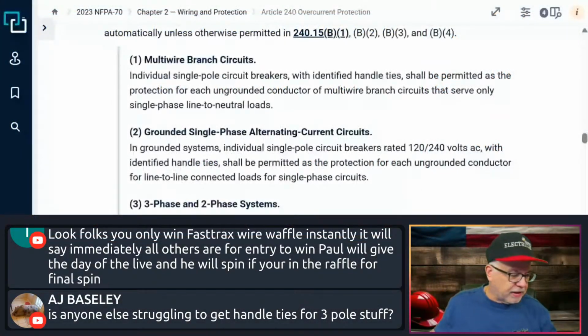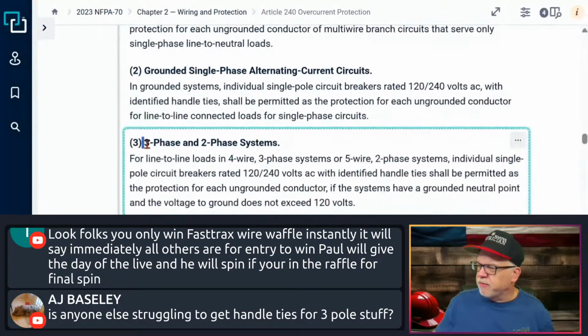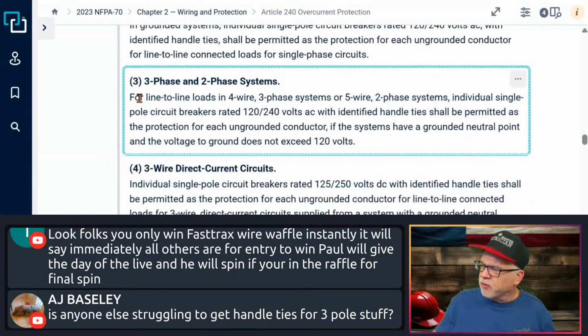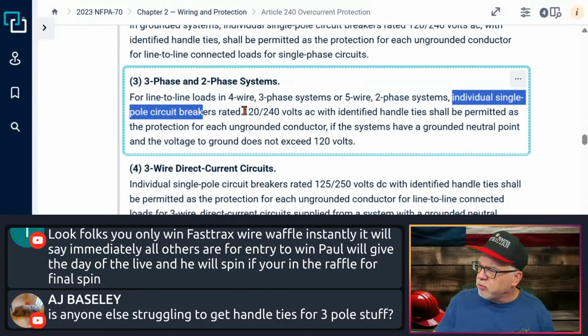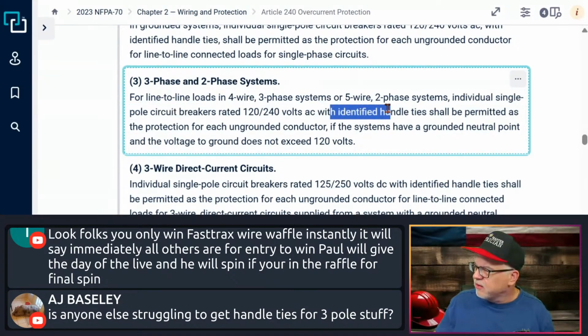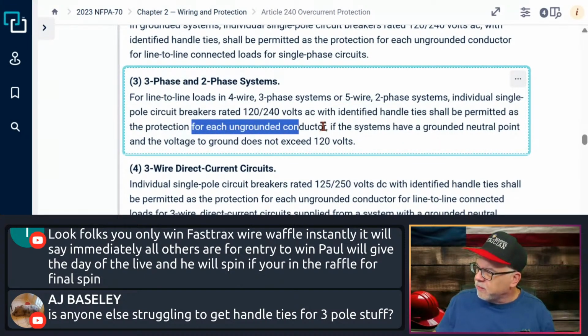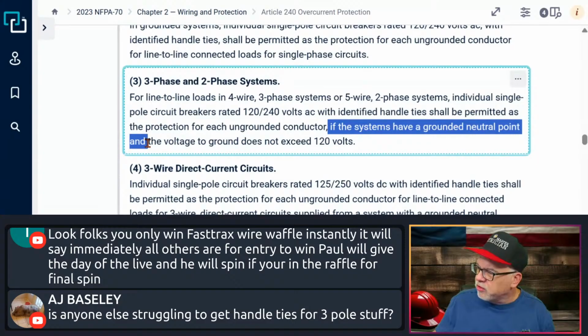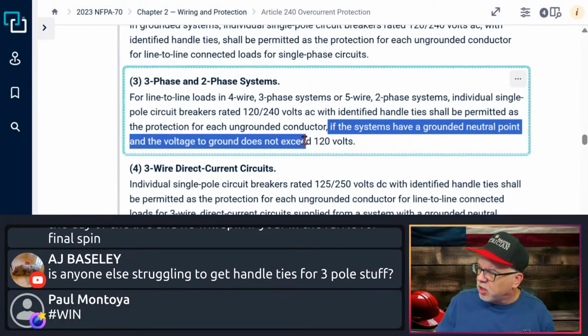All right. And then, of course, just so we cover it, let's go back here. Let me see if I can zoom this back out. Here also for three-phase, people ask these questions all the time. It says for line-to-line loads in a 4-wire three-phase system or a 5-wire two-phase system, it allows individual single-pole breakers rated 120/240-volt AC with identified handle ties. Handle ties shall be permitted as the protection for each ungrounded conductor if the systems have a grounded neutral point and the voltage to ground does not exceed 120 volts.